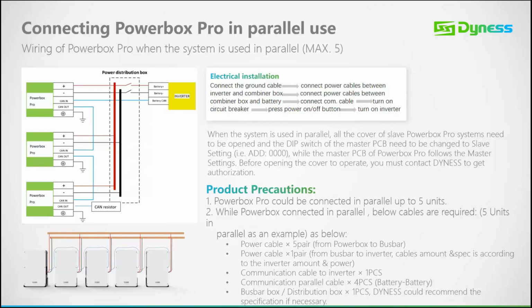So the electrical installation: connect the ground cable, connect the power cables between inverter and combiner box, which in this case is our busbar. Connect power cable between combiner box and battery, connect the communication cable, turn on circuit breaker, power on the master Powerbox Pro by holding the button for approximately 3 to 5 seconds, and your inverter will then turn on.